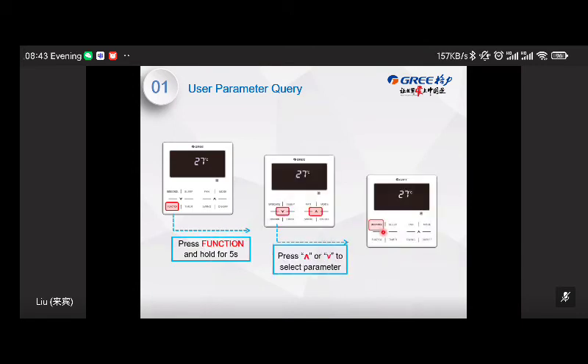And sometimes maybe our engineer and technician want to check some parameter from the wired controller. You can use this method. This is the operation for the engineer, for our after sales, for our technician. Press and hold this function button for 5 seconds, and then you can see here it will show you a C00. C means checking. Then you can press up and down button to change the parameter. Then if you want to exit this page, press enter or cancel to return to the previous page.